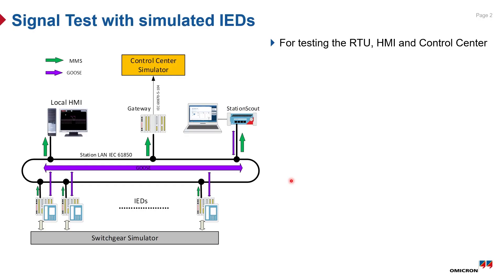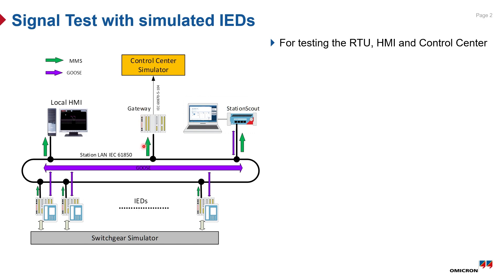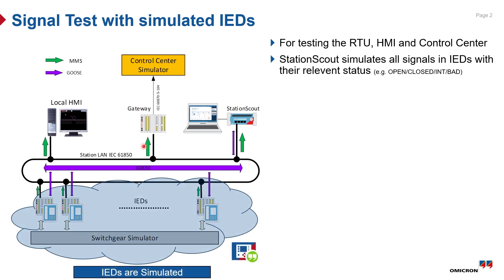Let's have a look at our system under test before starting. This is a typical substation utilizing IEC 61850 for GOOSE and reports. On the upper side you'll see the clients of the substation, such as a local HMI and the gateway for protocol conversion of signals to be transmitted to control center over 104. In our setup today, we have a local HMI running on a PC and Station Scout running on MBX and controlled by another PC.